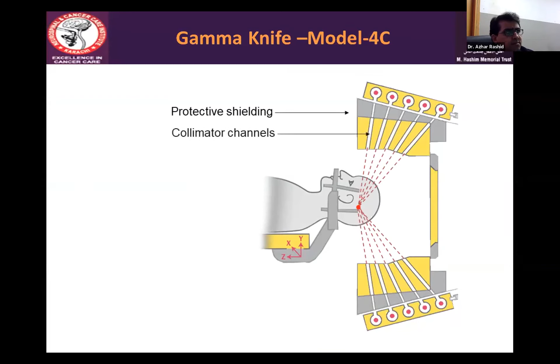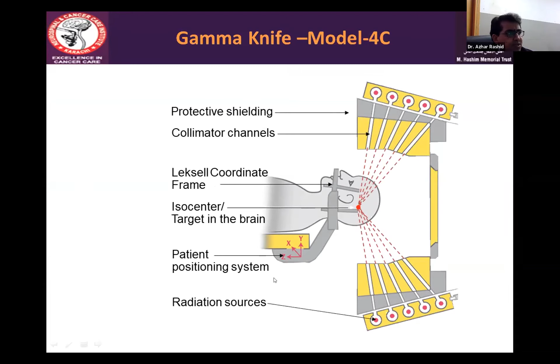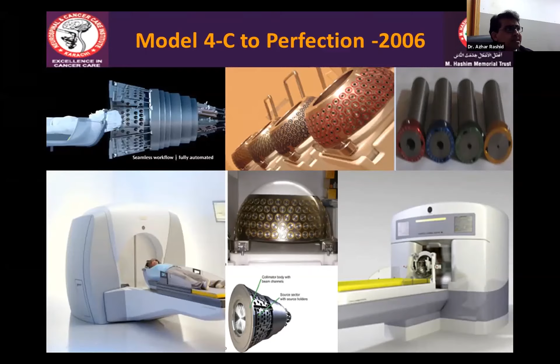And this model picture is showing different components: protective shielding, collimator channels, Leksell coordinate frame, isocenter target, patient positioning system, and radiation sources. And this model C was replaced by the model Perfexion, which was a game changer, having an automated system with different sectors and 192 sources of cobalt. The game changer was that the manual system changed to automatic, APS changed to PPS, 201 sources changed to 192, and there were 3 collimators having 8 sectors with 24 cobalt sources, and the changing time was only 4 seconds.